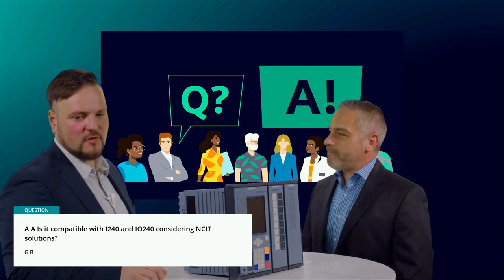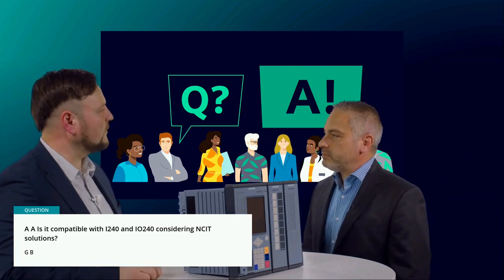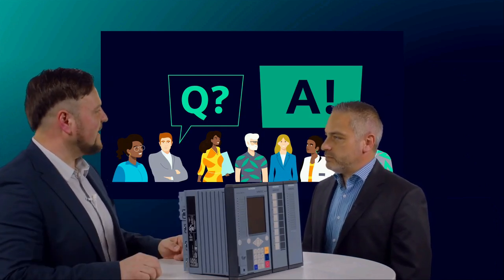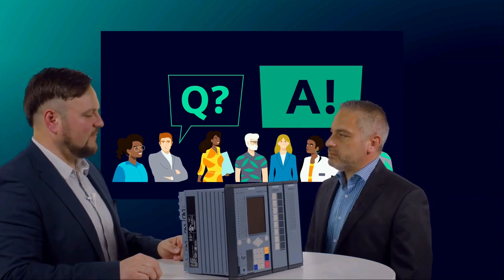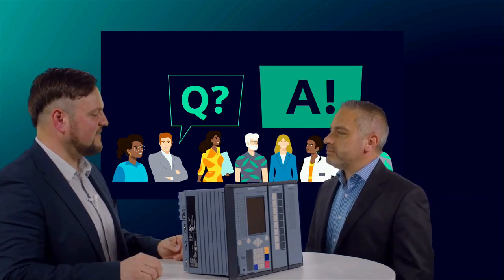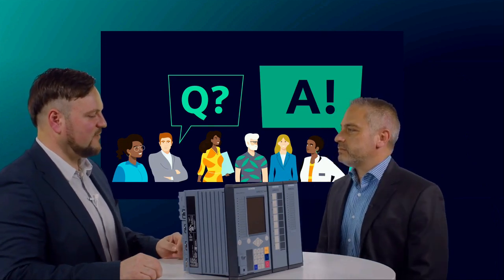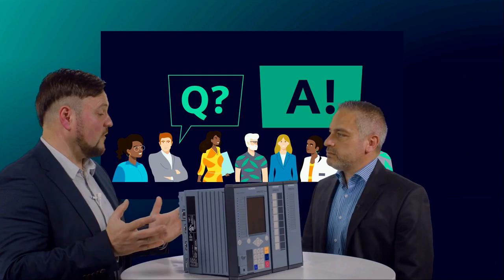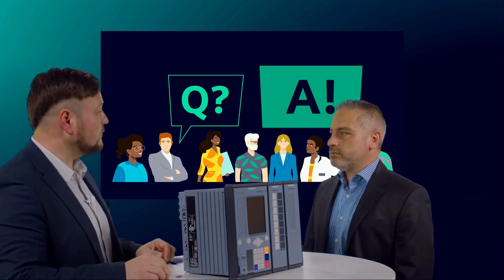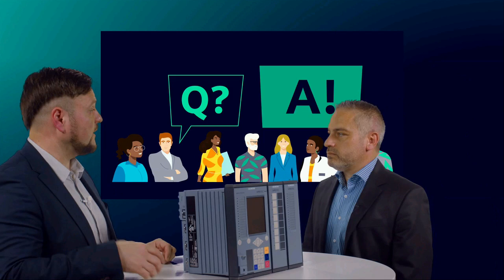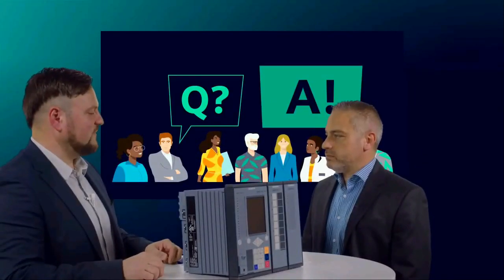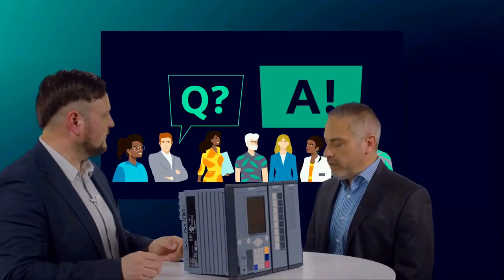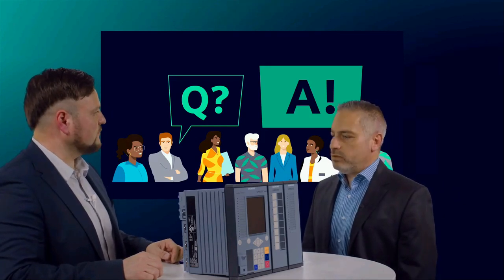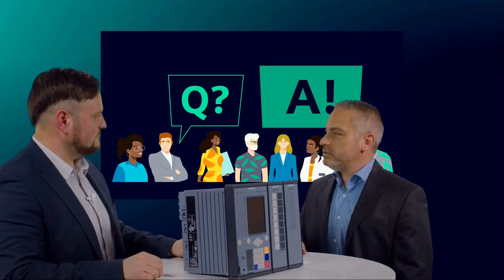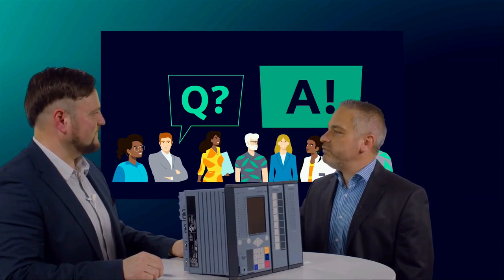When we talk about the IO240, we're talking about the Rogowski coil, the GIS Rogowski coil, CT or NCIT from the HV department colleagues, and this is already implemented and available. You can add this functionality, or this board, to our system, and the IO240 measures current and voltage. All our modules can be connected to the main module of the 7VU85.